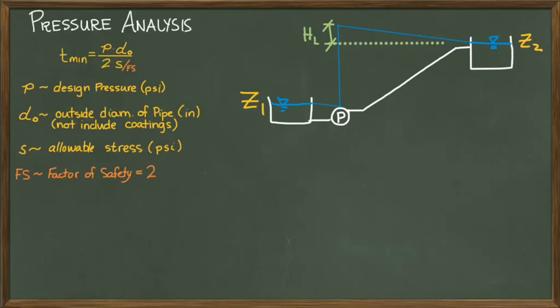When the pump is on, we add energy into the system to overcome the head loss due to friction and fittings. So when the pump is running, the maximum pressure occurs just downstream of the pump and can be calculated by converting the static head and the dynamic head into pressure units by multiplying by the unit weight of the fluid.